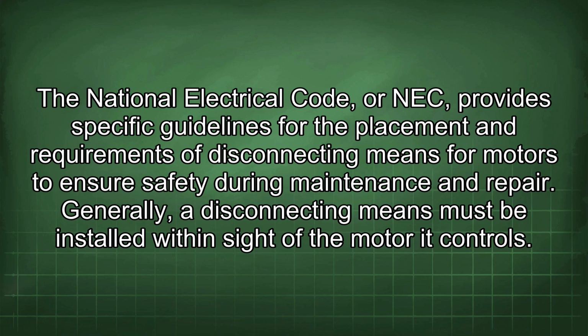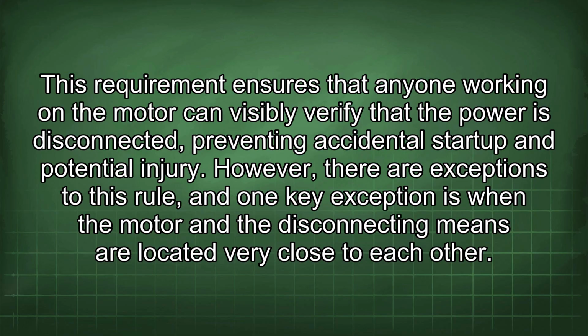Generally, a disconnecting means must be installed within sight of the motor it controls. This requirement ensures that anyone working on the motor can visibly verify that the power is disconnected, preventing accidental startup and potential injury. However, there are exceptions to this rule, and one key exception is when the motor and the disconnecting means are located very close to each other.